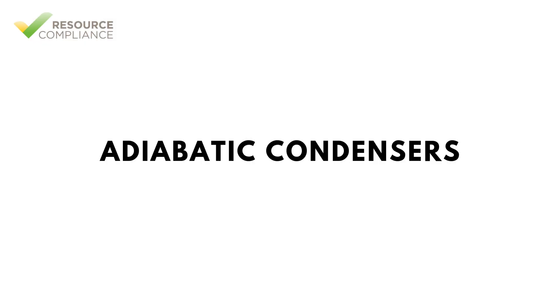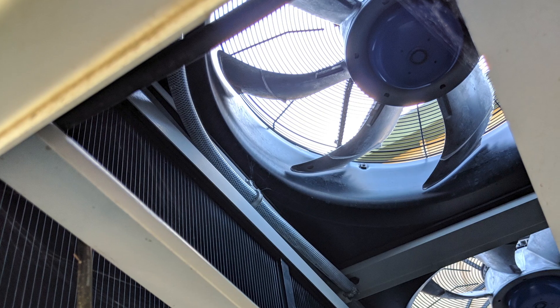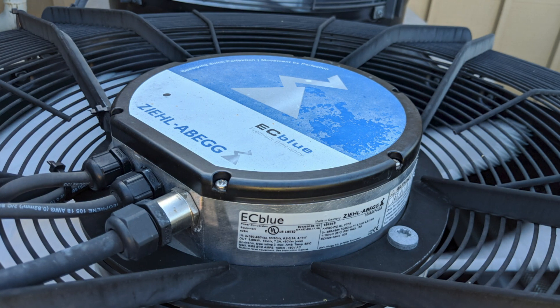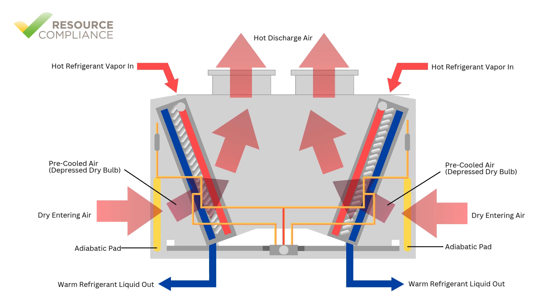An adiabatic condenser is a hybrid condenser that combines features of both air-cooled and evaporative condensers. When ambient temperatures are low, adiabatic condensers can operate in dry mode, where all heat exchange is accomplished through air movement without the assistance of water. When ambient temperatures rise, the condenser adjusts to adiabatic mode, where a water distribution system wets adiabatic pads, causing air drawn through them to cool via evaporation. The pre-cooled air then passes over the coils, enhancing the condenser's cooling capacity and maintaining efficient refrigerant condensation even in high-temperature environments.